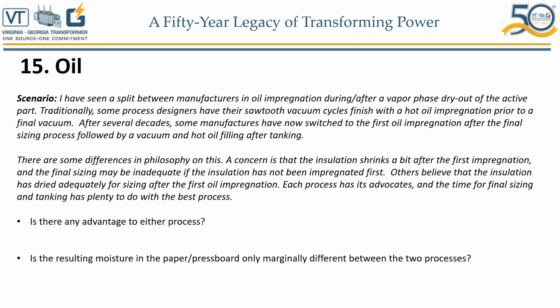Depends, really. As you said in the last part, the whole idea of drying an active part, core and coil, is to get the moisture content in the insulation below 0.5%. Vapor phase is known to be the best process to achieve that. The advantage of oil impregnation during vapor phase is that once you remove the active part from the vapor phase, there is that final pressing of the winding, applying the jacking pressure on the coils and then securing the coils using the core clamps and keeping them under pressure.